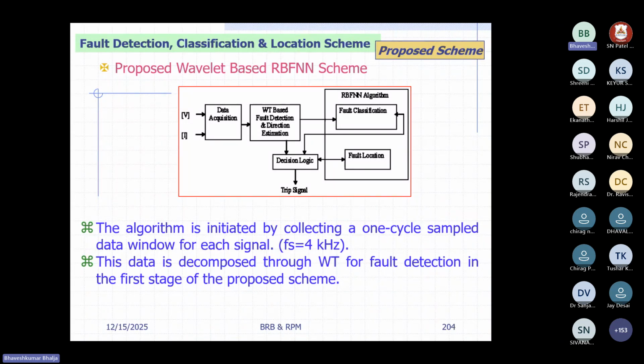So that output you can give to the decision logic, and the decision logic also works in parallel on the fault location part, that is, at what distance the fault has occurred. That command is also given to the decision logic. And finally, you can tell the display, you can tell the operator or utility person, because this time you have already isolated the circuit breaker, right?